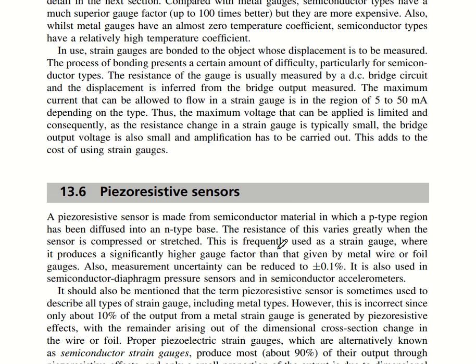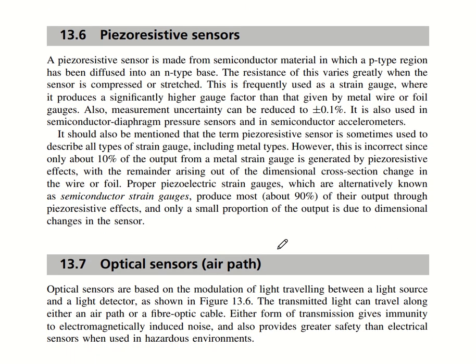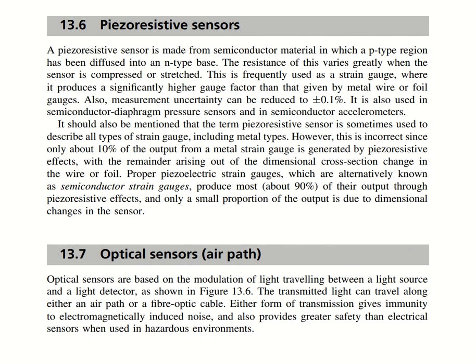Strain gauges are bonded to the object whose displacement is to be measured; bonding presents some difficulty, particularly for semiconductor types. The resistance of the gauge is usually measured by a DC bridge circuit and displacement is inferred from the bridge output. The maximum current allowed to flow is in the region of 5 to 50 milliamperes depending on the type. Since resistance change is typically small, bridge output voltage is small and amplification is required, which adds to the cost.